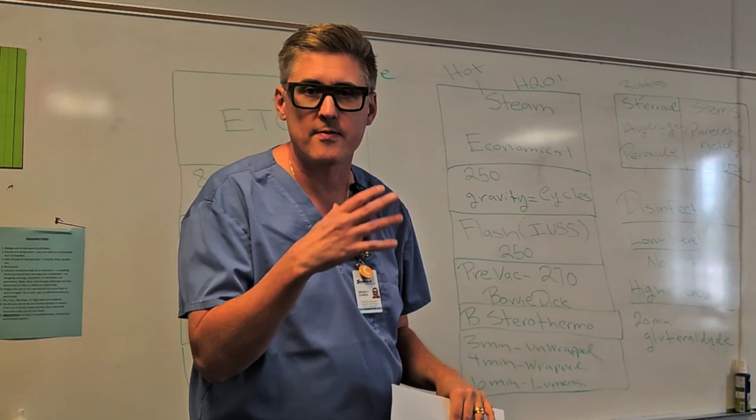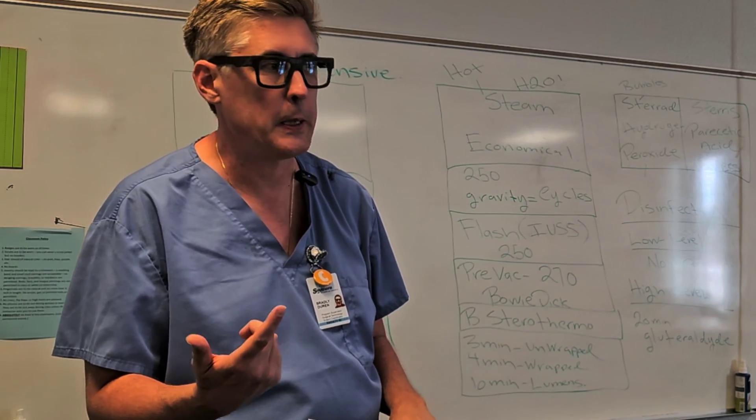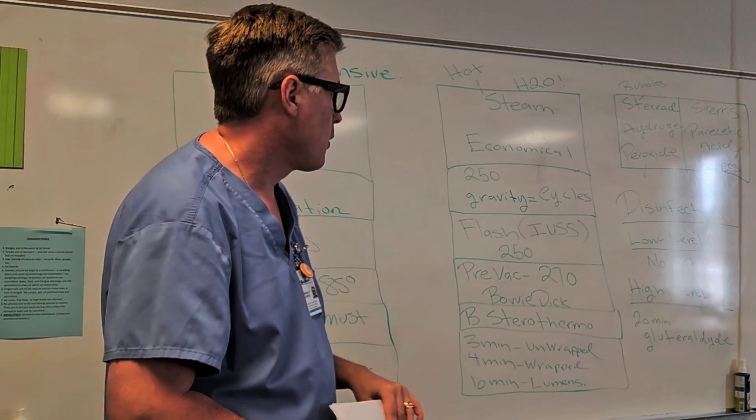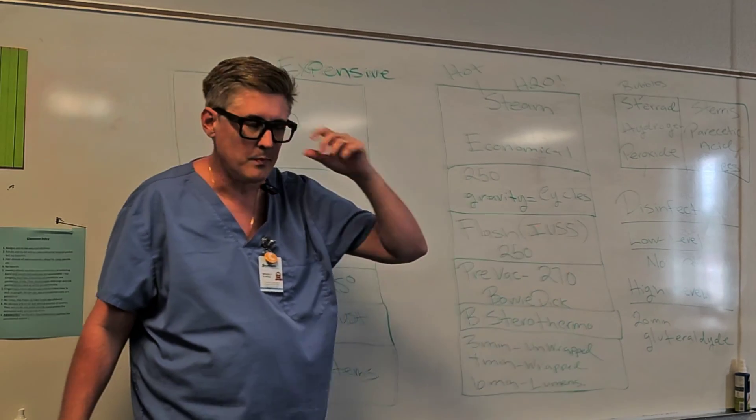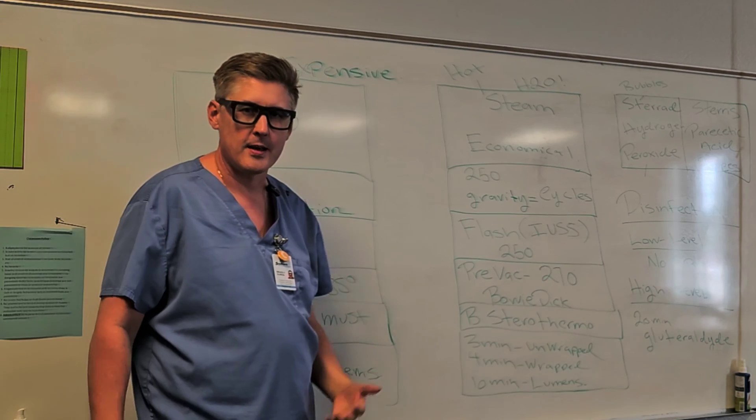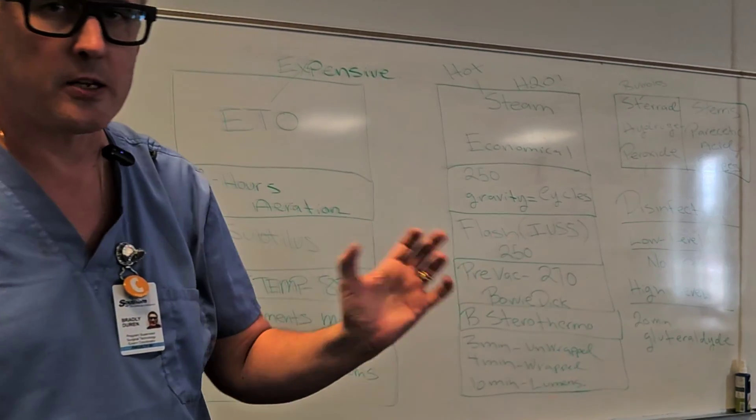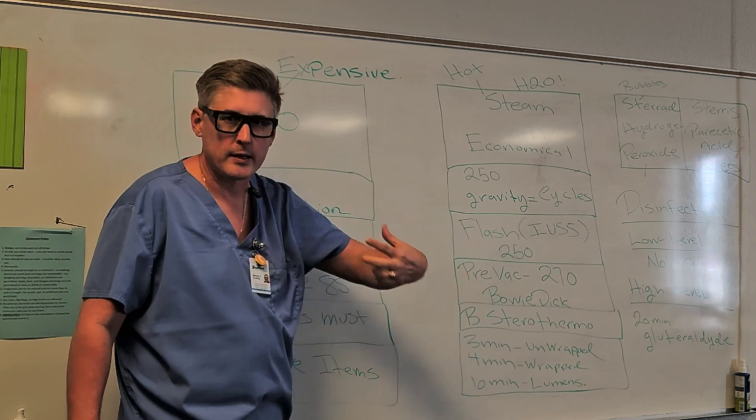Now, what is a flash sterilization, which uses steam, but flash? You know, in surgery, sometimes we need items that are emergency, not an implant. You cannot flash an implant, but items that you need because the case can't continue unless you have this item. The patient's in jeopardy. We steam it off at a high temperature quick for lower temperature times. And I'll go over that a little bit, but that's what a flash is. So your research is, what is an IUSS? You probably know it already, but once you do some research on what an IUSS is. It's not the SS Minnow.